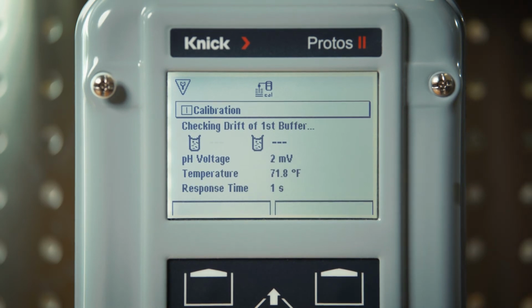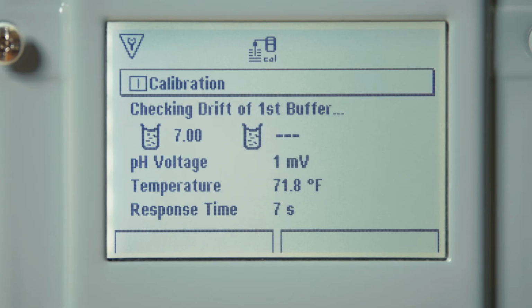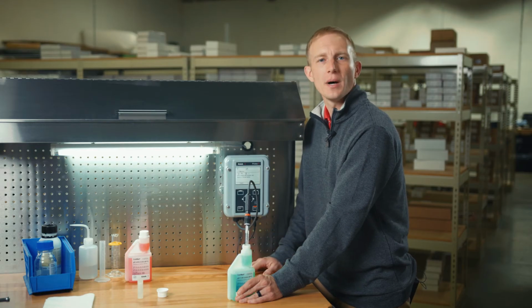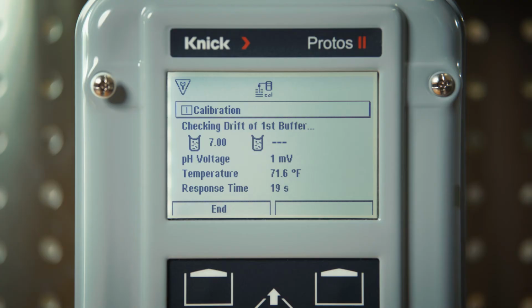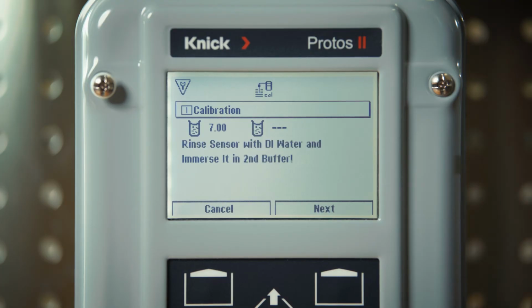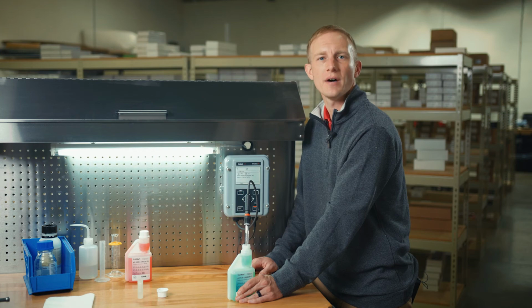After pressing Next, the transmitter will begin to check the drift of the sensor in the first buffer solution. You can see that the buffer value is automatically recognized. The raw pH voltage value is displayed along with the measured temperature and response time of the electrode in the buffer. Once finished in the first buffer solution, the transmitter will prompt you to once again rinse the sensor and immerse it in the second buffer solution.